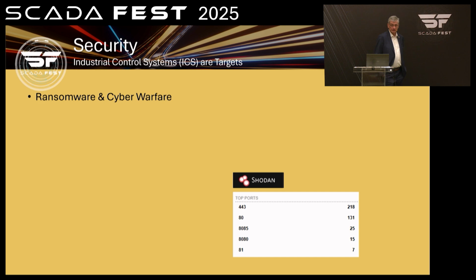We've had some positive stories, one system was on the internet, the backup server wasn't, it was just talking through VT SCADA's RPC port. The one on the internet got corrupted and shut down. The backup server ran fine, so they reformatted the main one, did a get from server, and everything was back up and running. So that's a good story.